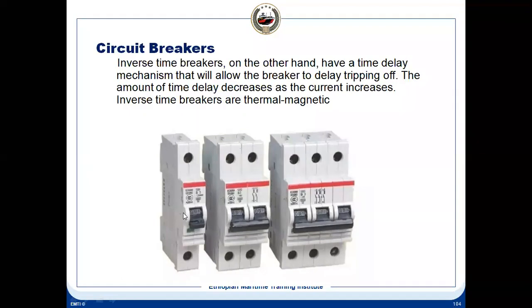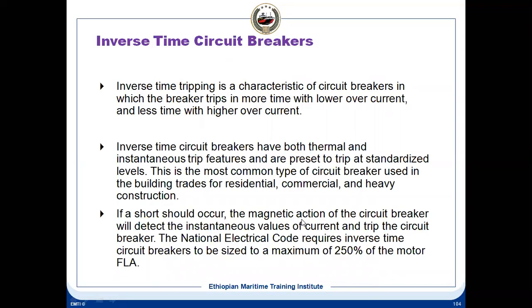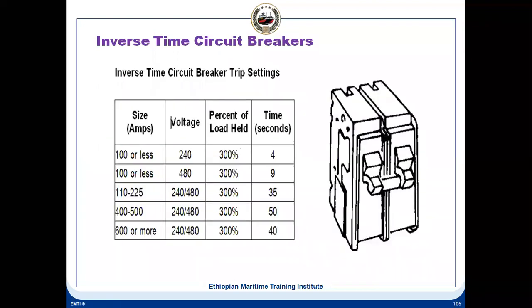So here you can see single pole, double pole, 3 pole. Inverse time tripping is a characteristic of a circuit breaker in which the breaker trips after more time with lower current and less time with higher current. Instantaneous means immediate. Inverse time breakers have both thermal and instantaneous trip features and are preset to trip at the standard levels. So this is the inverse time breaker.